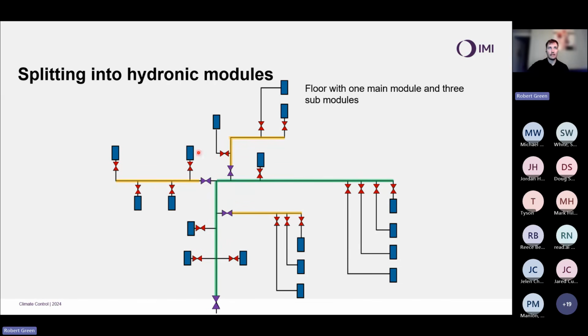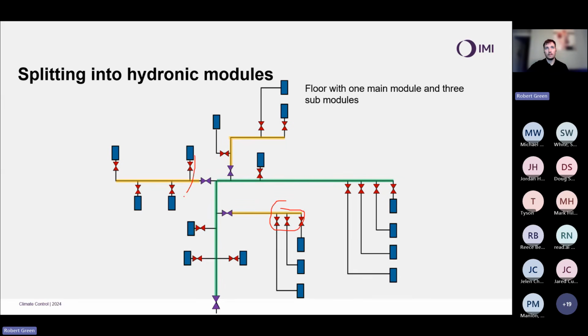I can then do the same function on these 3 and on these 4. And then I know via the proportional law, when I adjust these 3 partner valves, my modules will also be adjusted in proportion. So all of the valves in the module. So in essence, if I want to balance this system, the first thing I would do is here, so then here, then here, and then I can balance this main module back, the partner valve on the floor. I can carry out that exact same exercise on all of my floors, and then finally balance the floors against each other, again exploiting the proportional rule and ensuring I have optimally balanced that system and made the system operate 100% of design flow in all areas whilst adding the minimum amount of pressure drops.